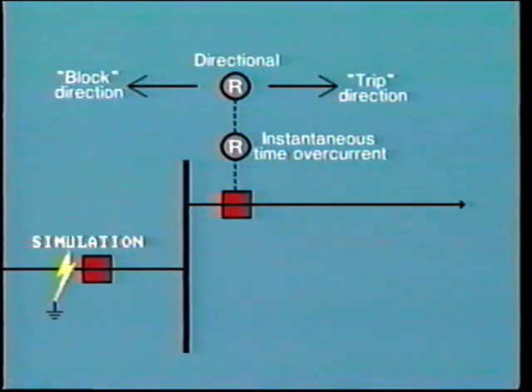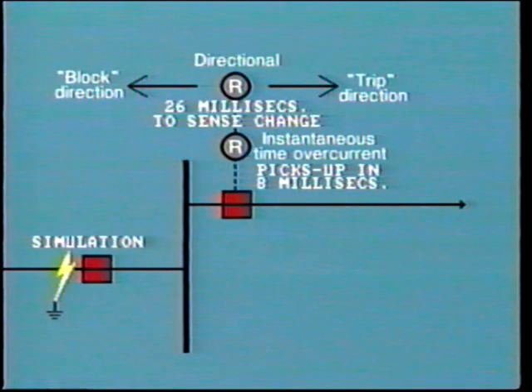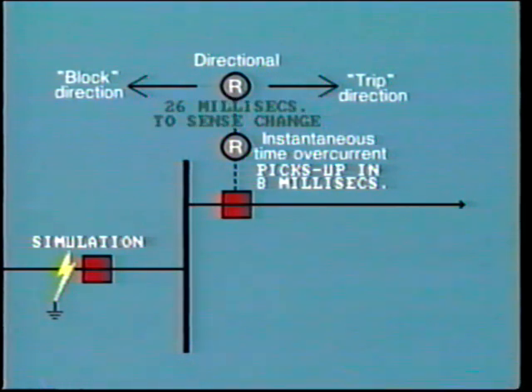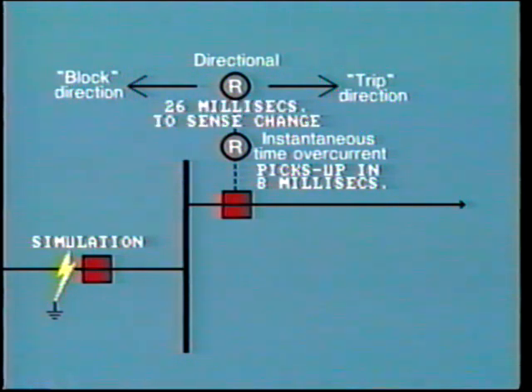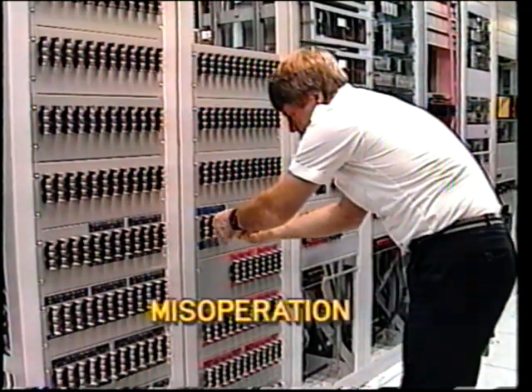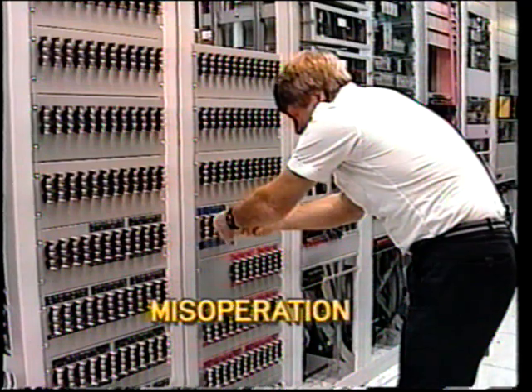When a fault occurs, the instantaneous relay picks up in 8 milliseconds. But with pre-fault power in the operate direction, the directional unit takes 26 milliseconds to sense the change in direction of power flow. Consequently, the blocking from the directional unit is too late to prevent the instantaneous relay from tripping the line. This misoperation is due to several causes.